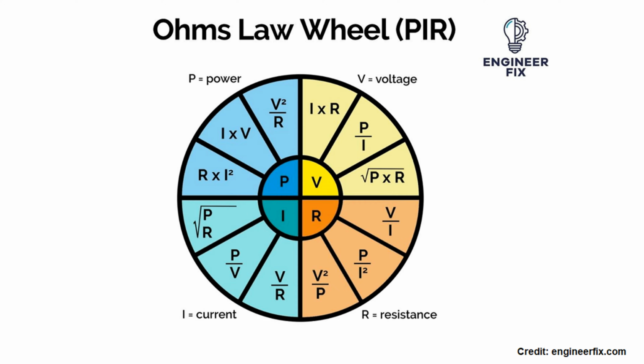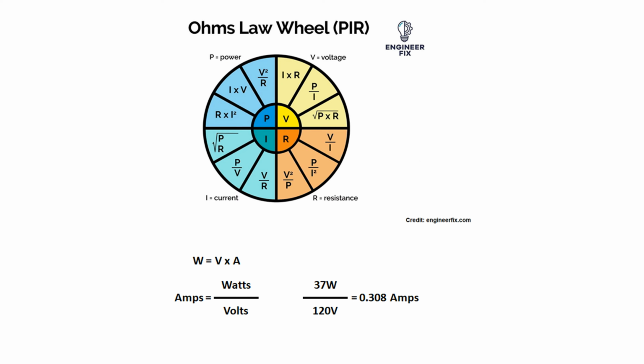Let's calculate the expected motor current using the familiar Ohm's Law wheel. The HVAC duct booster is rated at 37 watts. So, referring to the power quadrant of the wheel, we can say watts equals volts times amps, which means amps equals watts divided by volts, and the current quadrant of the wheel agrees. The motor's 37 watt rating divided by 120 volts equals 0.308 amps. So I can base my fuse size on 0.308 amps, right?